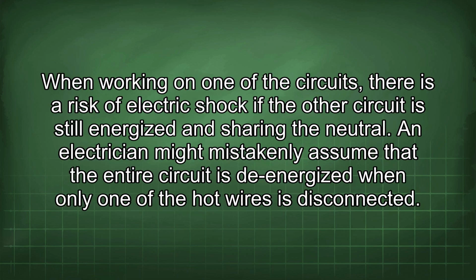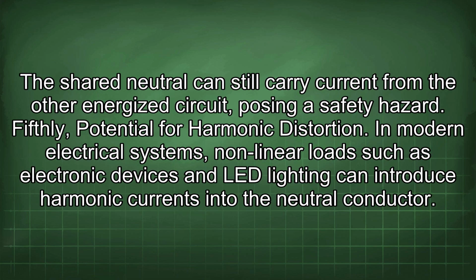When working on one of the circuits, there is a risk of electric shock if the other circuit is still energized and sharing the neutral. An electrician might mistakenly assume that the entire circuit is de-energized when only one of the hot wires is disconnected. The shared neutral can still carry current from the other energized circuit, posing a safety hazard.